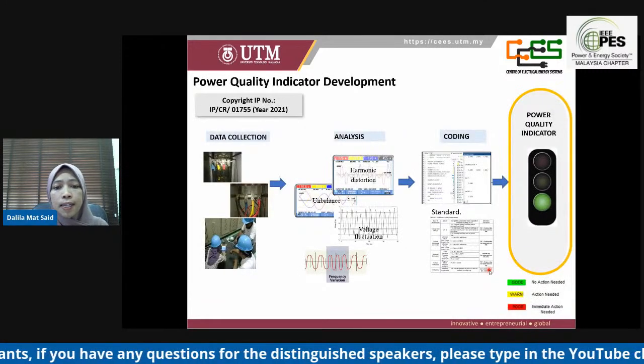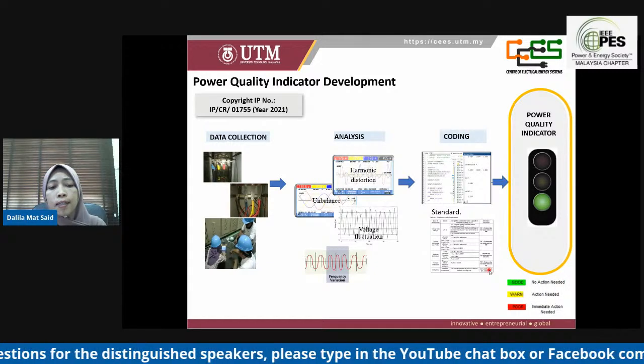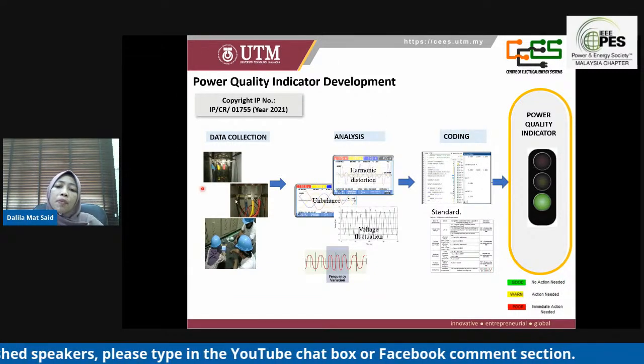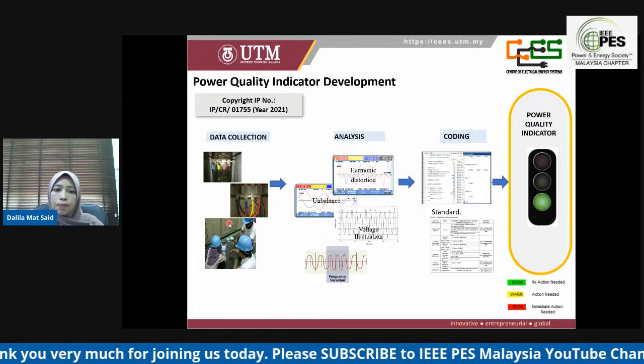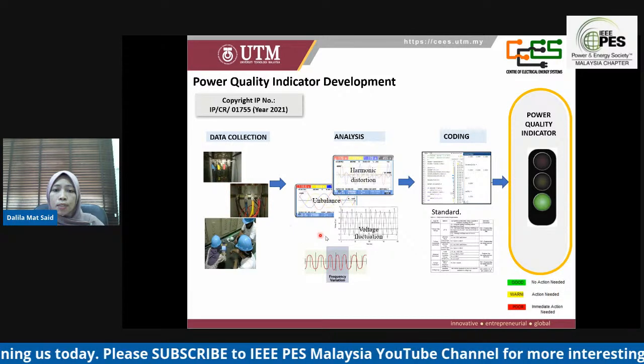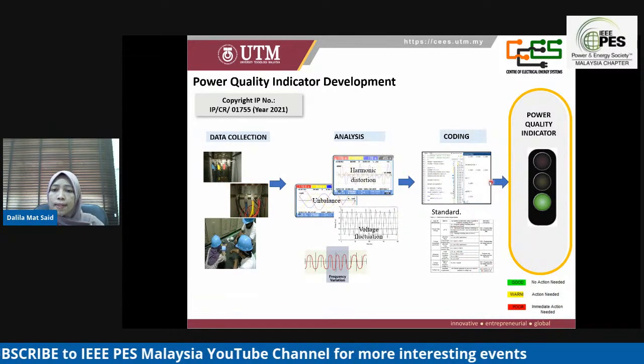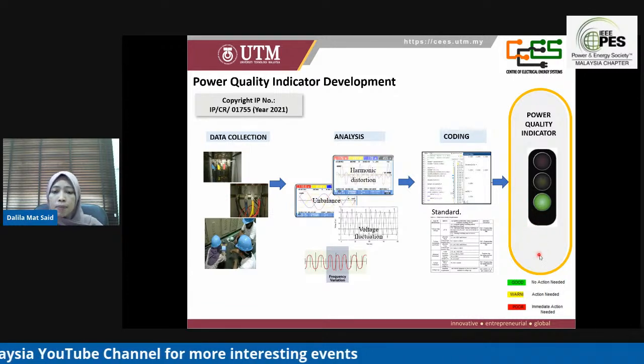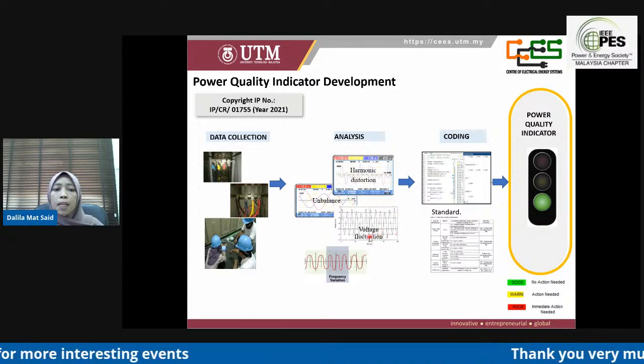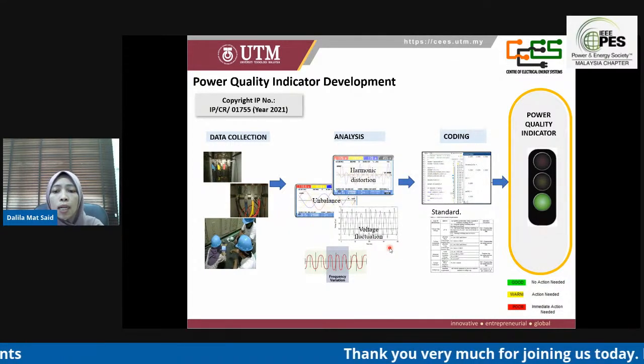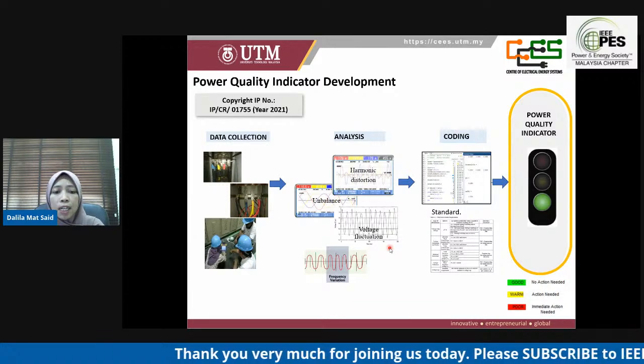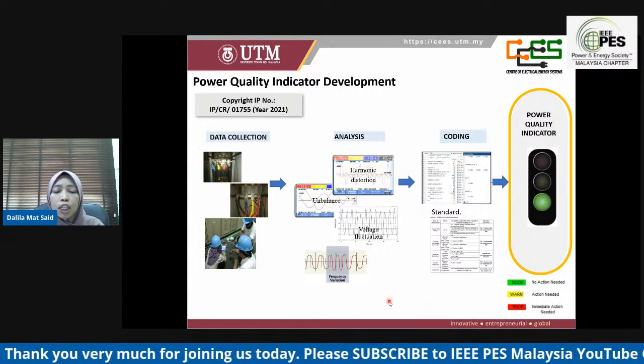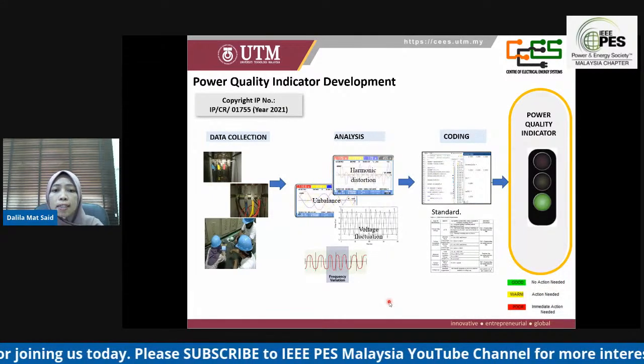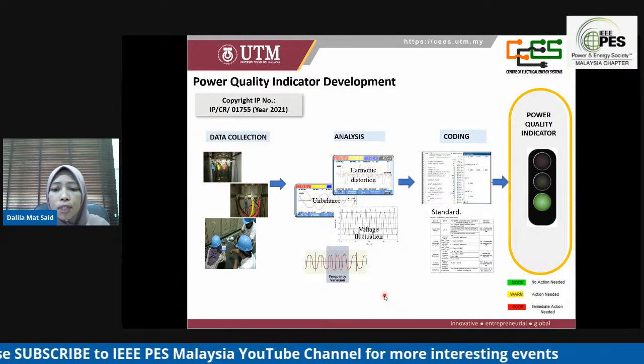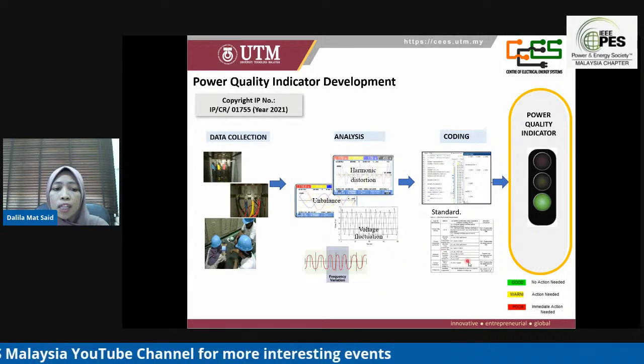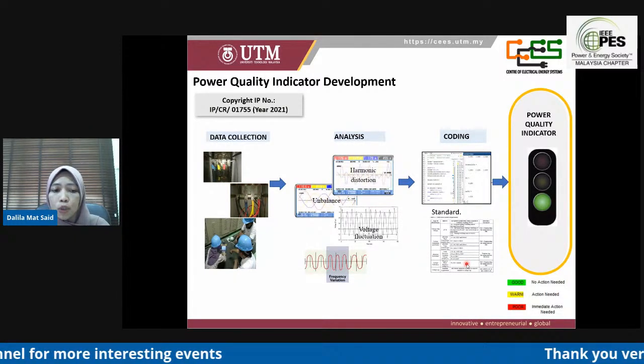So this indicator, the power quality indicator, is designed purposely to identify the performance level of power quality at the substation. It starts with data collection, analysis, and coding, and comes up with an output that indicates the substation's performance. The percentile method is used to determine the individual power quality characteristic. The compatibility level for the power quality problem is defined in terms of the 95% percentile being lower than a certain value. It can be defined for all continuous phenomena such as flicker, voltage variation, and total harmonic distortion.